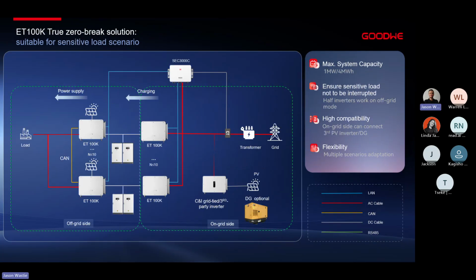Next, and new to GoodWe, is the ET100 True Zero Break solution. So this is 0 millisecond transfer or a full off-grid supply while using our inverters and supplementing load from the on-grid side as well. So how this works is we DC-DC combine two inverters together to a battery stack or two battery stacks, and we run all of our loads in off-grid operation constantly.